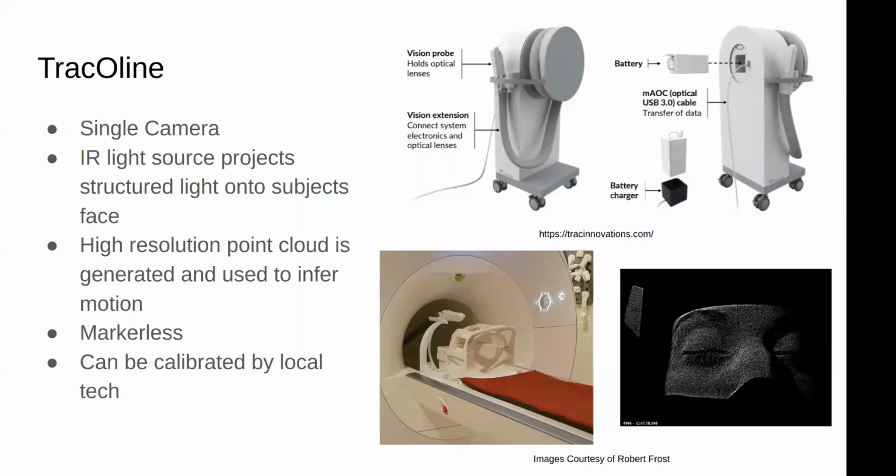And it's a per subject calibration, correct? It's not per subject, it's per camera mount. So per camera mount, okay. Yeah, so in theory, if you could mount the camera in the morning and then no one ever hit it or knocked it, you wouldn't have to recalibrate. In practice, it can be a little difficult getting the top of the head coil on and off and getting the patient in and out without removing the camera. So we tend to do it per subject, but technically speaking, it's every time you mount the camera or change the position of the camera.